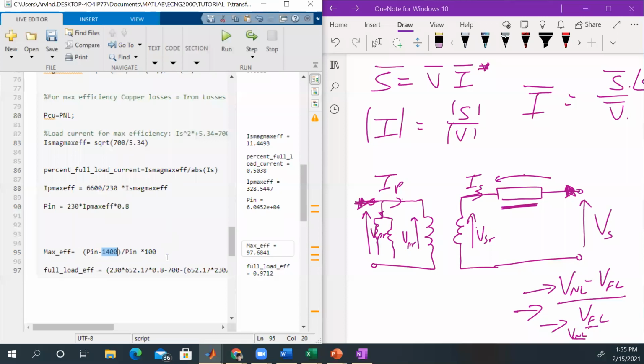Then you have PN minus P losses over PN, and you get the efficiency at 97.68%. If we calculate the full load efficiency from before, with the currents we had earlier, you'll see it is 97.12%, so not a huge difference in efficiency.